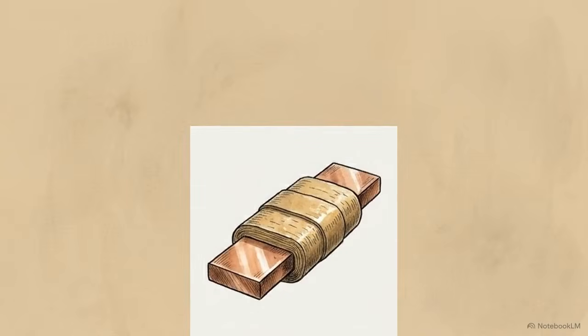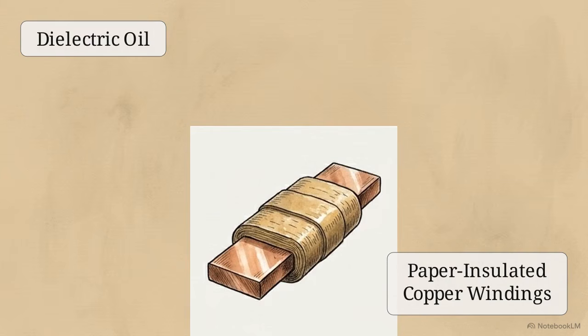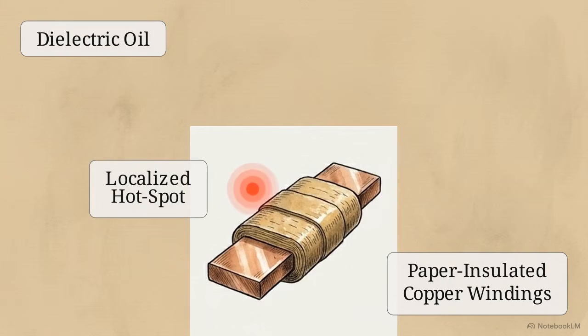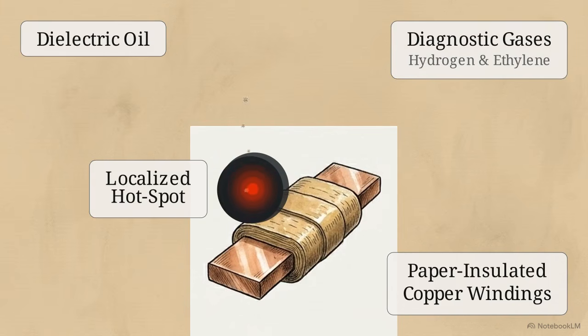This animated diagram shows a cross-section of paper-insulated copper windings. When a localized internal fault occurs, it creates an intense, glowing hotspot. That extreme heat chemically breaks down the oil and solid paper insulation. This produces diagnostic gases, like hydrogen and ethylene, forming small bubbles.